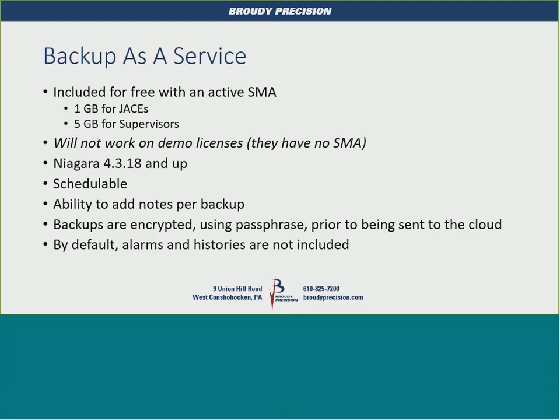So once scheduled, it'll just sit there and back up your JACEs all the time? Yeah, Tridium's recommendation for that is every 30 days, especially if you're not doing histories and alarms. Not much is going to change structurally in the station.